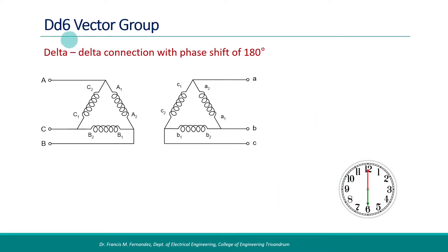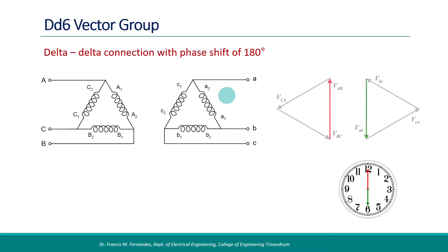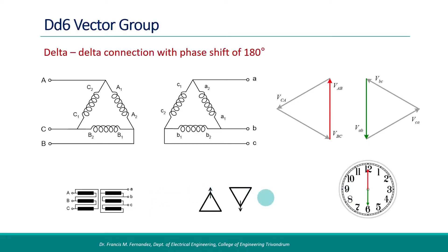Similar is the case with the DD6 vector group. Both the primary and secondary are delta connected, but the polarity of each winding is reversed in the secondary side — on the primary side it is A1, A2, and on the secondary side it is A2, A1, and similarly in other windings as well. This results in a 180-degree phase shift in all the voltages — again a 6 o'clock position. The simplified connection diagram and the displacement diagram are shown.